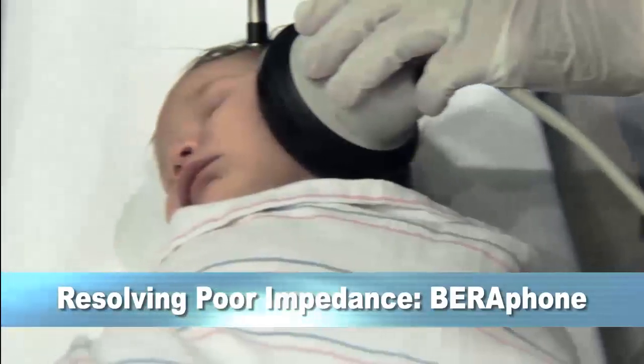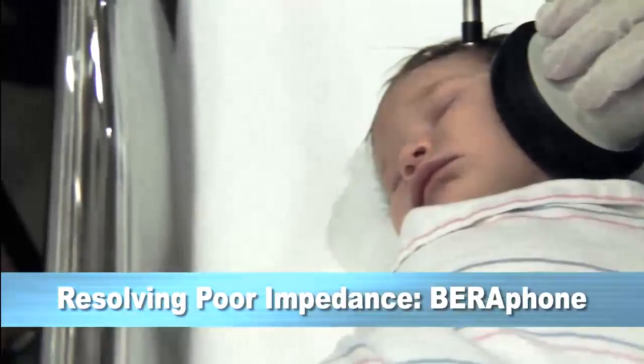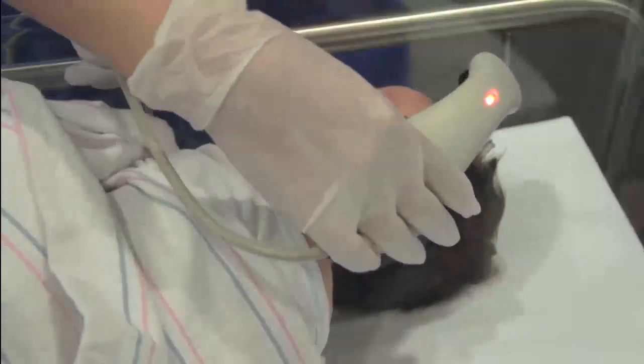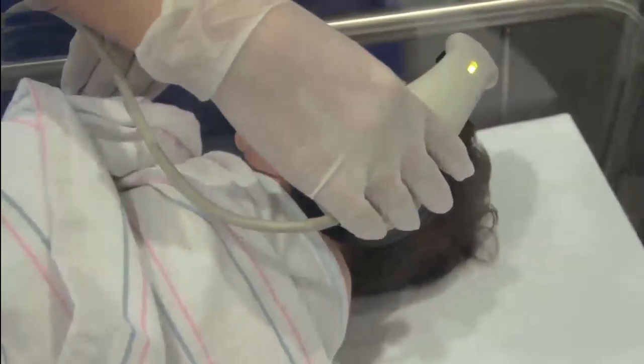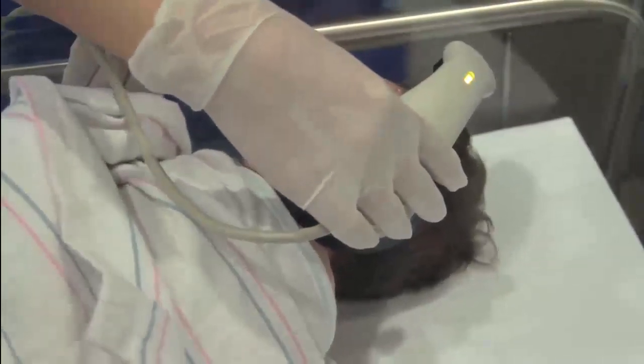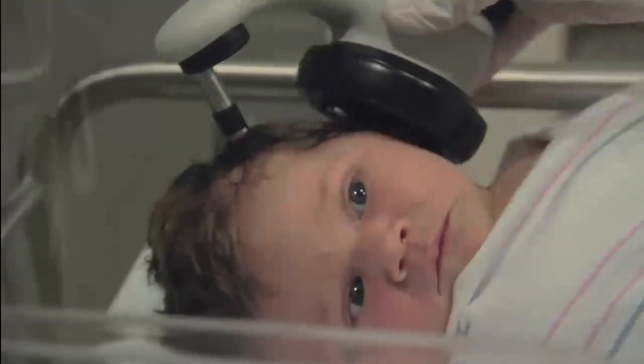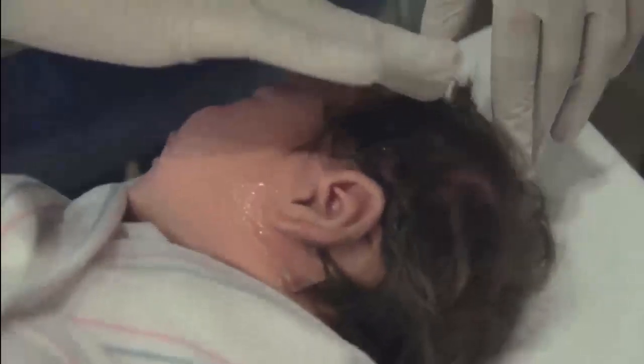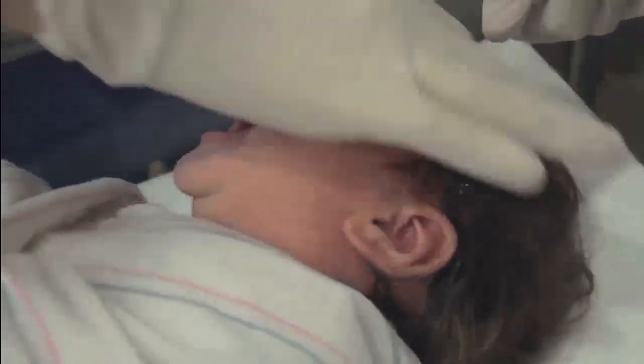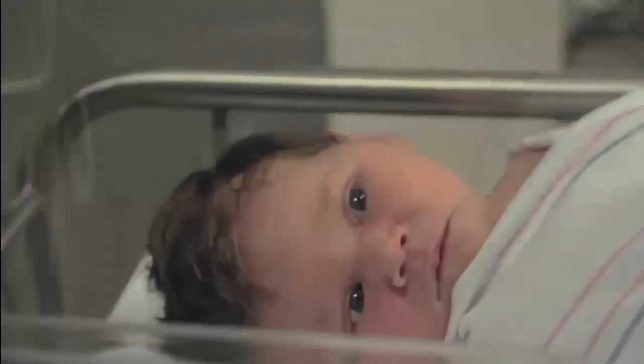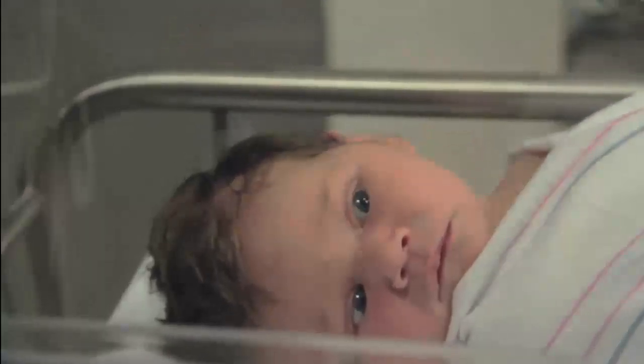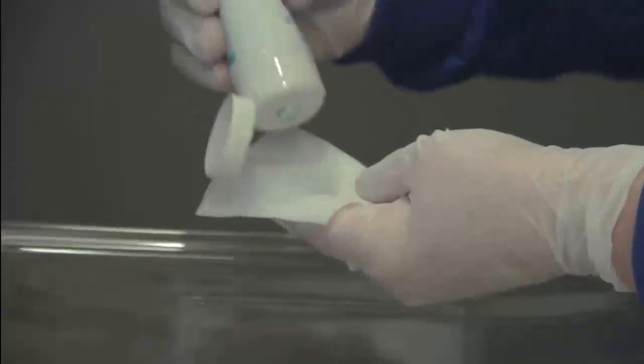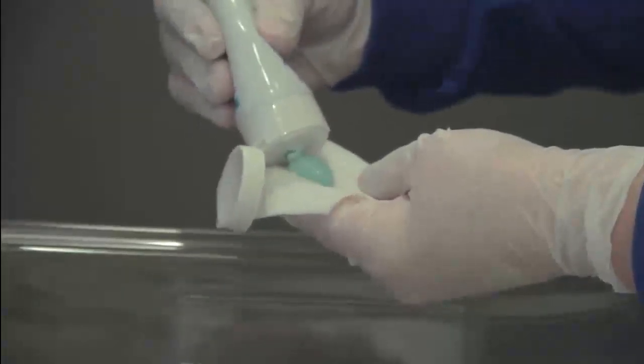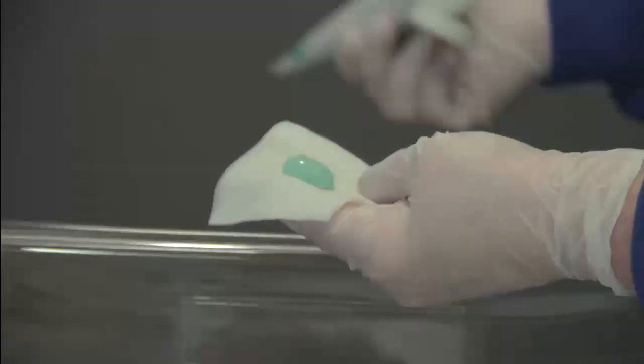To resolve poor impedance at one or more of the electrode locations, check that the BERAphone is resting on the skin that you prepared with the electrode gel. Move the position of the BERAphone electrode slightly to see if you can achieve improved impedance. Lift up the electrode that shows poor impedance and massage a little more gel into the skin. If good impedance can't be achieved with the electrode gel, rub a small amount of NuPrep electrode skin prep, which is slightly abrasive, into the skin at the site and try again.